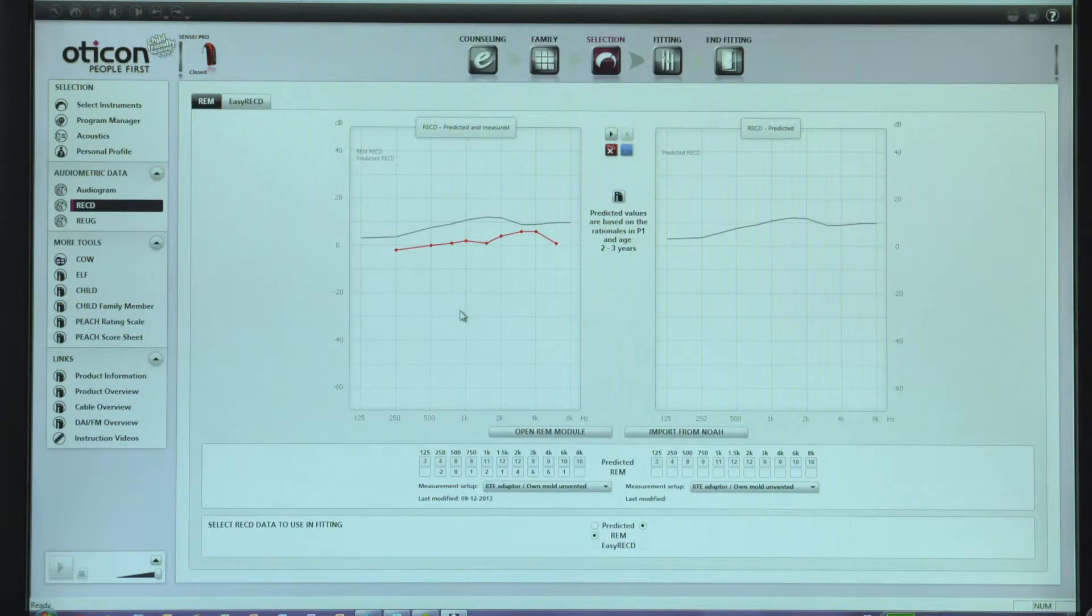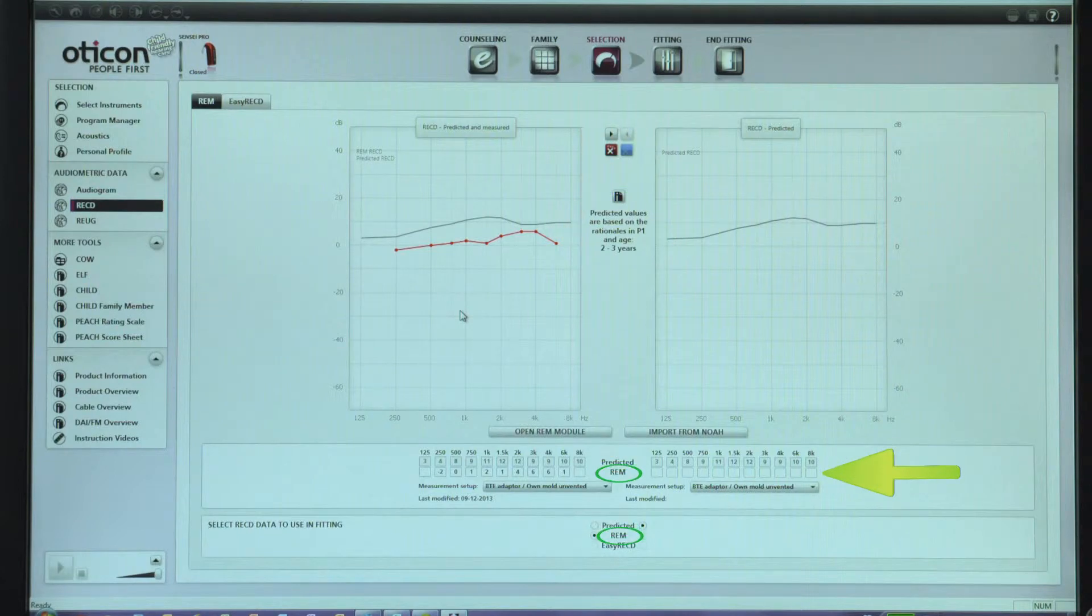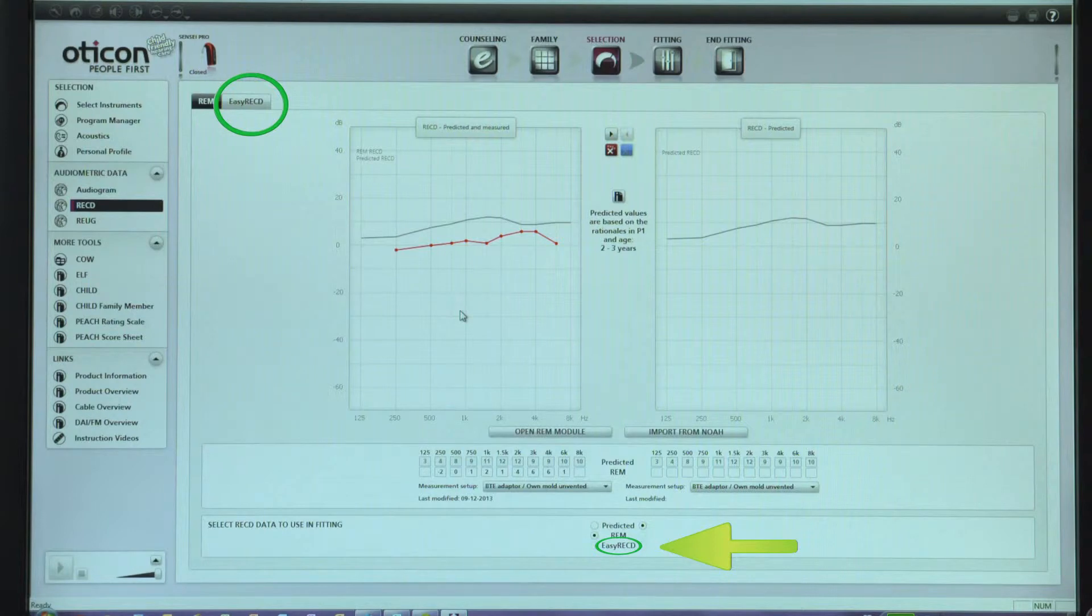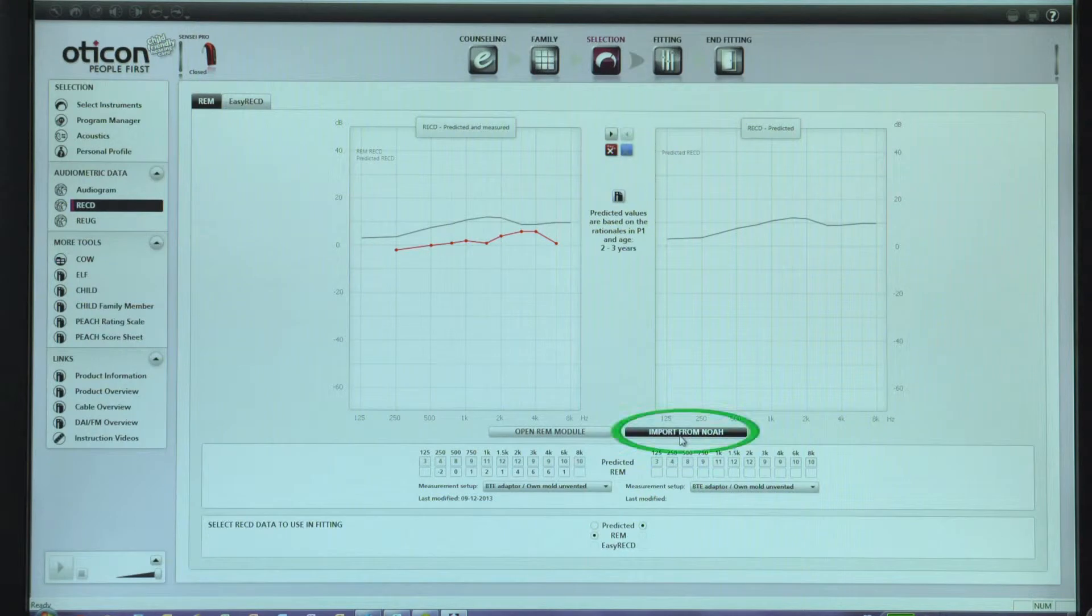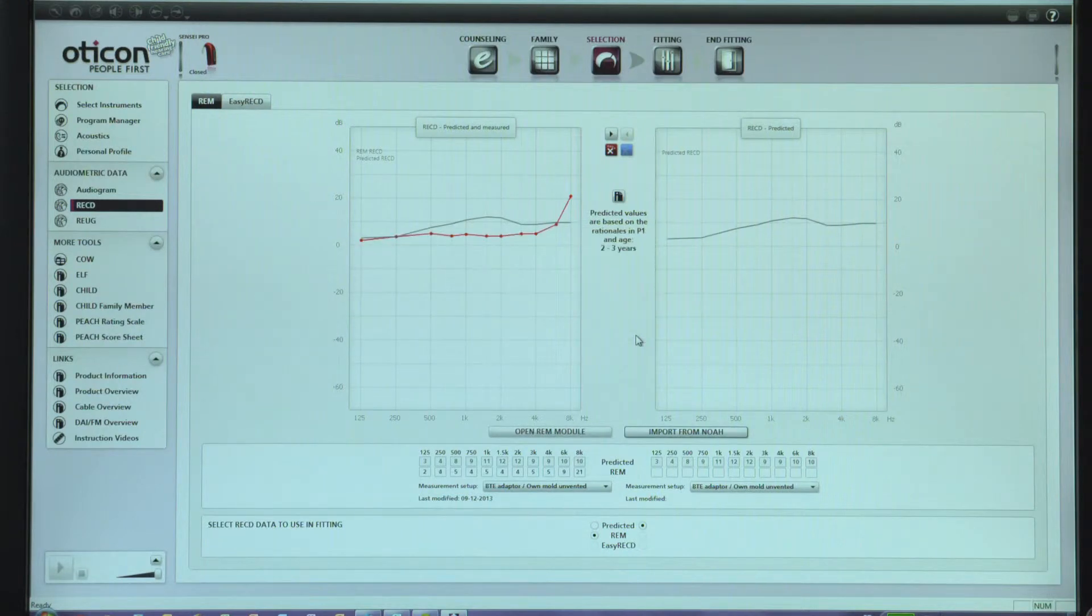Here we can either use an age-appropriate predicted RECD or enter a previously-measured RECD. Alternatively, the easy RECD tool in Sensei Pro is another way of accounting for individual ear acoustics, especially when no measuring equipment is available. This example shows how to use previously-measured RECD data, which was saved in NOAH and then transferred into Genie using the Import from NOAH button. Once the measured RECD values have been transferred into Genie, the software will recalculate the fitting and take these into account.